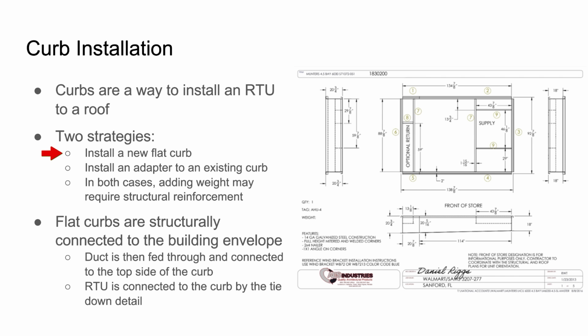You can install a flat curb, which is literally flat all the way around. That requires you to set the taper yourself, meaning you reinforce the curb in some way, usually with pressure-treated plywood or steel, to get it level. You don't want to set a unit off level — it won't drain properly. Most roofs have a taper in them, so you need a taper in the curb. The unit has to be level, but the roof has its own pitch, so you have to match that.